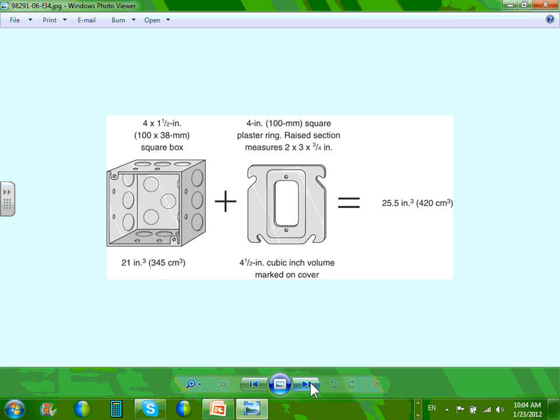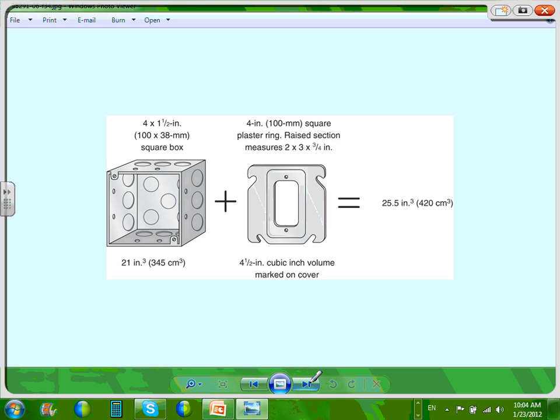conductors. Box fill calculation, and we're not doing box fill calculation because we did it before, guys. If you have a raised plaster ring like this one, where you're going to put your sheer up around there, you're going to add the cubic inch of the box into the cover. The box and the cover have to be added together when you size how many conductors you can bring to this box. We did that one last quarter, right? You guys remember that one? When we have a raised cover, it gives you more room, so you have to add the room that's specified with that raised cover.